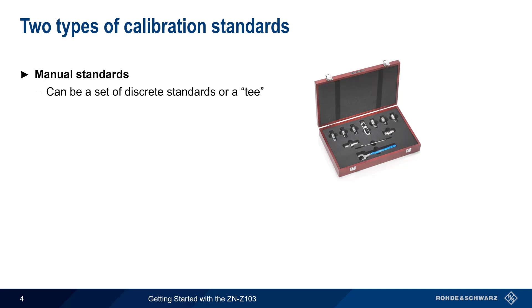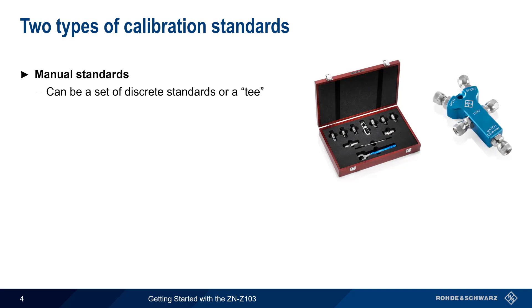There are two general categories of calibration standards. Manual calibration standards are delivered either as discrete standards or in the form of a kit that combines these standards into a compact and portable unit. These are called manual because the user manually connects and disconnects each of these standards in turn during the calibration process.